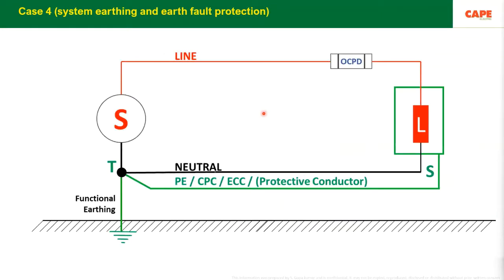Very, very important. Number 4, earth fault protection. What is earth fault protection? Now I am showing you a TN-S network. Means you have a source, you have an OCPD, which stands for MCB, you have a load. The green is nothing but the body of the equipment, and then you have a protective conductor connected back to the neutral of the source.